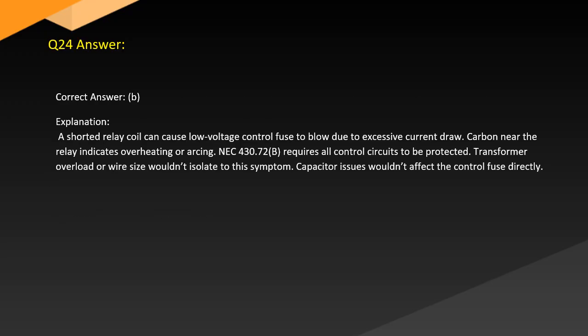Answer. Correct answer, B. Explanation. A shorted relay coil can cause the low voltage control fuse to blow due to excessive current draw. Carbon near the relay indicates overheating or arcing. NEC 430.72(B) requires all control circuits to be protected. Transformer overload or wire size wouldn't isolate to this symptom. Capacitor issues wouldn't affect the control fuse directly.